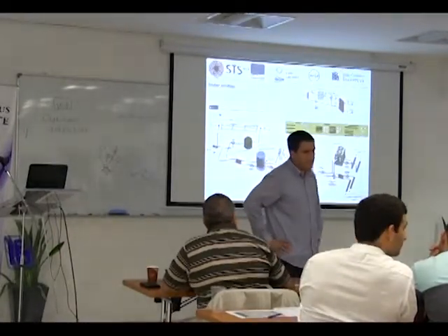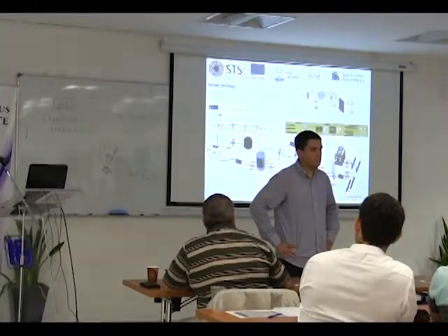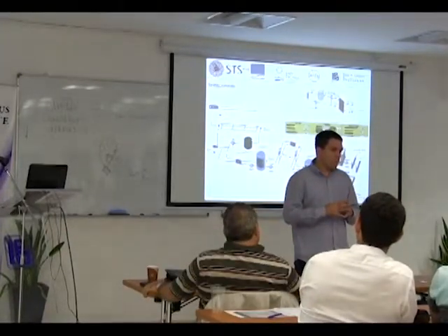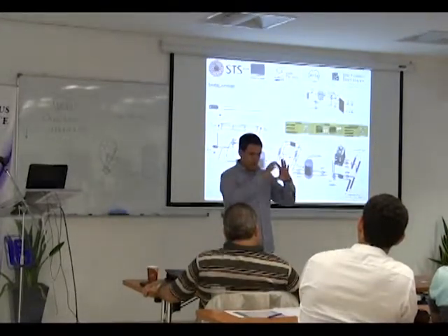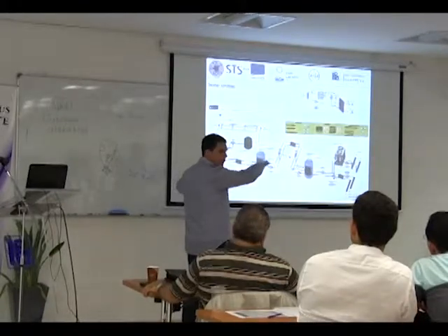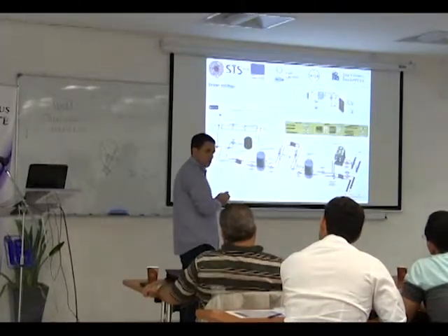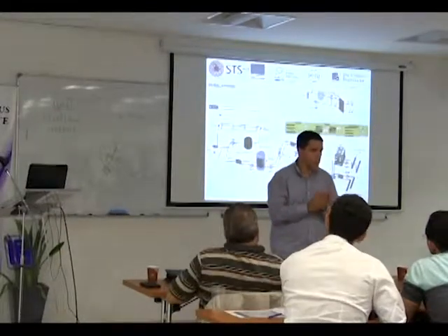Q: About keeping the system at high flow? A: We want a turbulent flow. This was discovered during field testing in Italy. When the sun is high and the absorber tube inside the vacuum tube is cold, some parts heat more than others — differential thermal stress. The absorber tube is four meters long. At high flow rates, the flow is more turbulent, providing better heat exchange inside the pipe. So yes, we want to maintain high flow to ensure turbulent conditions and avoid the absorber tube bending.